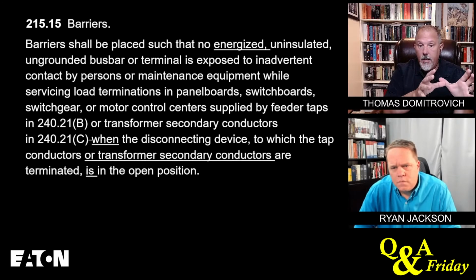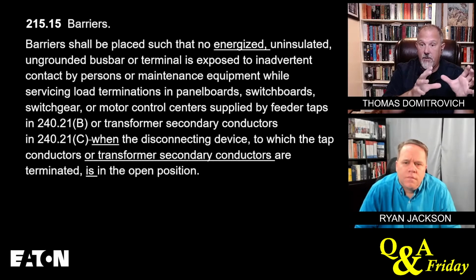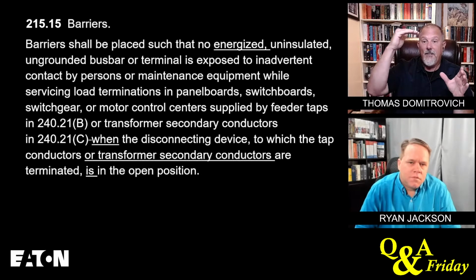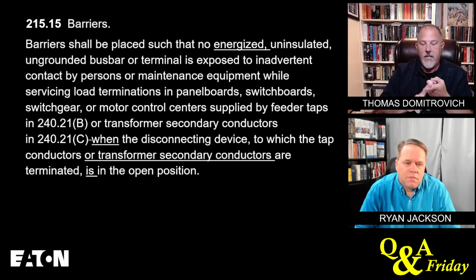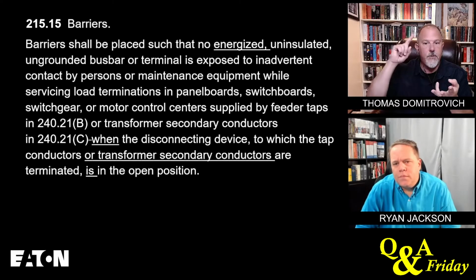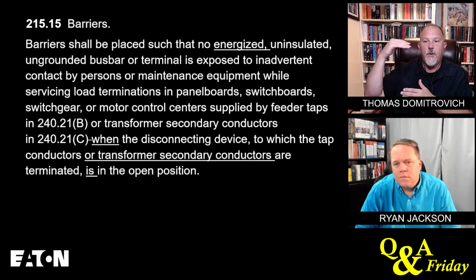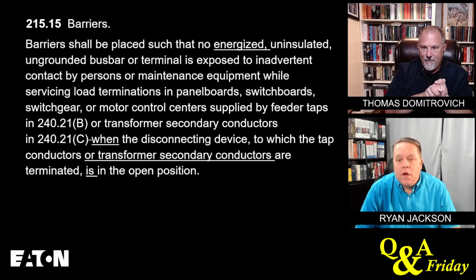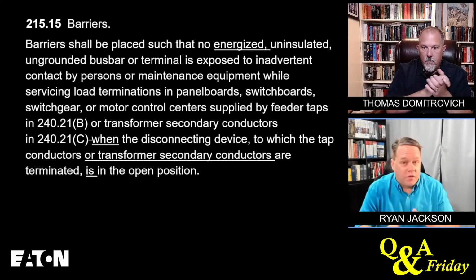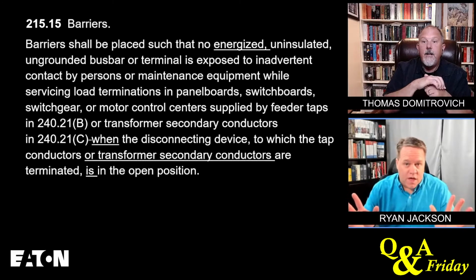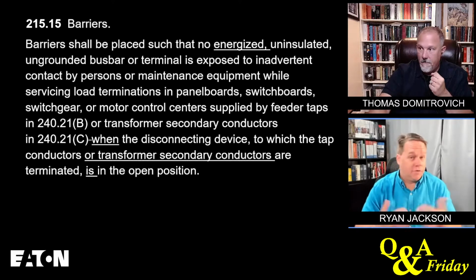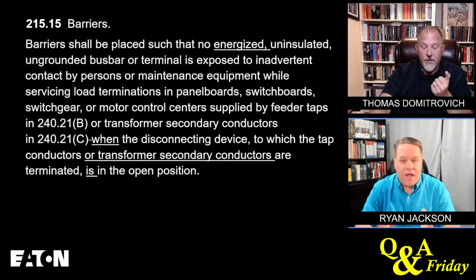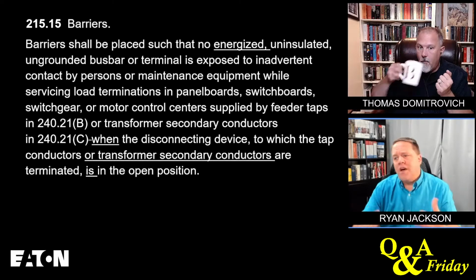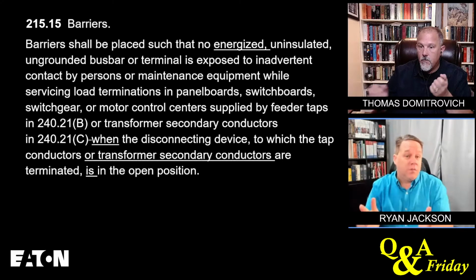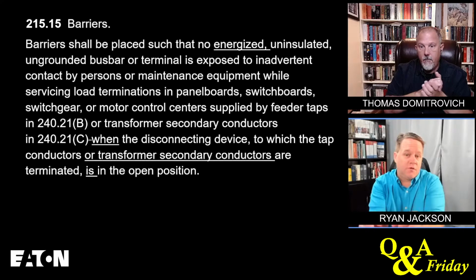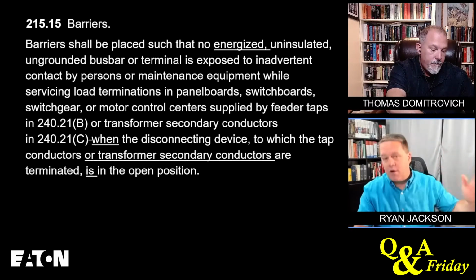Because what you're doing with the barrier is reducing the likelihood of causing a fault in that secondary piece of equipment. And the severity is still high, whether that piece of equipment is connected to a delta-Y ground, all that jazz. The clearing time for a fault on the secondary is still going to be a long time. Yeah, and I agree. The concept of having the barriers at the service equipment, I absolutely love that change when it was put in 2017. I thought, here's a solution that we can provide for $2 that removes a real hazard. On service conductors, it's especially important because I can shut off the main breaker and everything downstream of the breaker is off. But those service conductor terminals are on unless I call the utility and have them come out and shut off power.